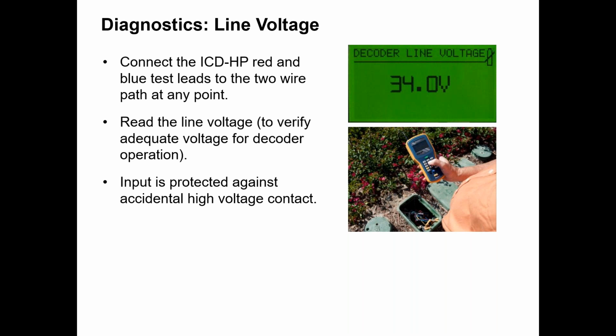Another function on the ICDHP is, if you hook your red and blue test leads to the 2-wire path, you can see your exact voltage. If you try to do it with the meter, sometimes you'll see it bouncing around. The ICDHP is actually synced, so you can see the exact voltage at any time. And that is definitely helpful because then you can see if you're low 2-3 volts, you might have a broken wire, or if it's too high, that could be damaging, and it might be something at the controller level itself. The input is protected against accidental high voltage contact, but still be careful when you're hooking into it.